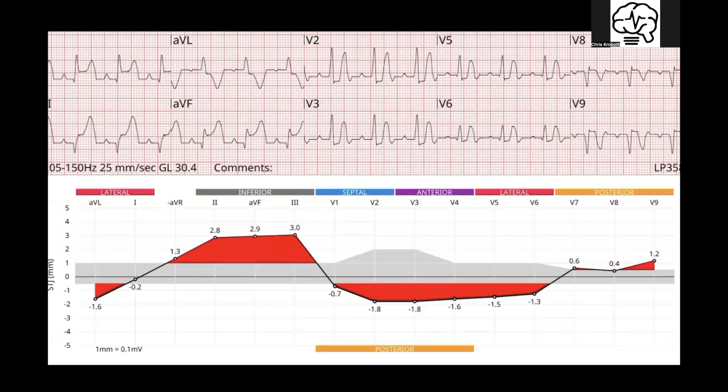Here's the example of the high-res STJ insight graph at the bottom — look how crisp this is in comparison to a thermal printer in the back of your bag. We're always asking for things to be lighter, thinner, smoother. It is 2024 — you have a tablet on your rig. It is very easy now to just transmit over, super quick, super reliable, and you have it right there. You can send it off, take a screenshot, annotate it if you want, zoom in and zoom out. That's the LifePack 35 transmit feature over to a tablet, and I just wanted people to see what it looks like if you don't utilize the printer function — how seamless it is, and how crisp it is in terms of good diagnostic quality and clinical assessment.